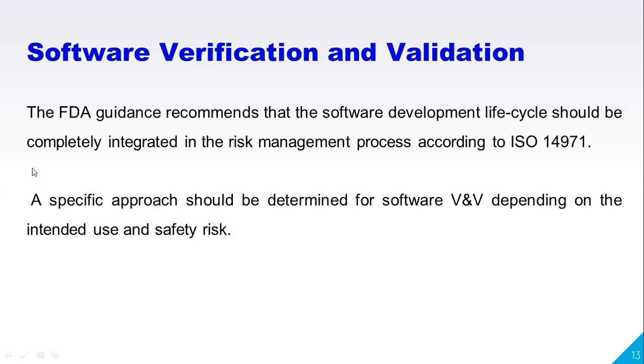For that also, the FDA gives guidelines. The FDA guidance recommends that the software development lifecycle should be completely integrated in the risk management process according to ISO 14971.